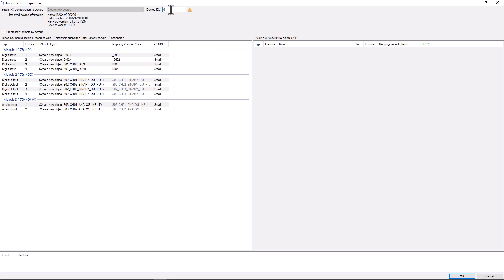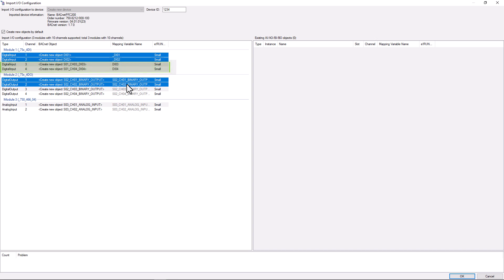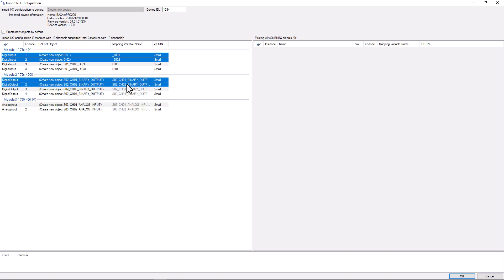Now we have to assign a device ID that is unique on the network. You can then select the desired modules using the usual options. At this point, we also find the names previously assigned in the controller configuration as designations for the new BACnet objects to be created: first the group with underscore without prefix, then the group without underscore with prefix, and then the I/Os that we have not assigned a name to, with the name created by the configurator.